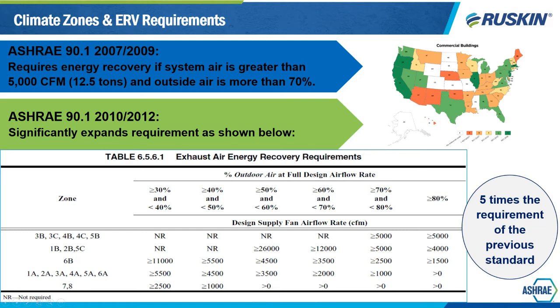When you go to ASHRAE 2010, it significantly expanded the requirements. The table below outlines it, but what you see here is that instead of having energy recovery requirements at 70% outside air, they actually dropped it down to 30%. So you started seeing some energy recovery requirements when you were only bringing in 30% of outside air. That is five times the requirement of the previous standard. If you look at 4A, where Kansas City is, and I was bringing in between 30% and 40% outside air, if my system is greater than 5,500 CFM, I am now required to have energy recovery. Next slide.